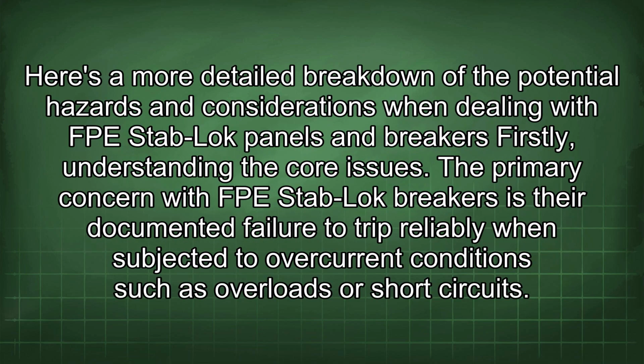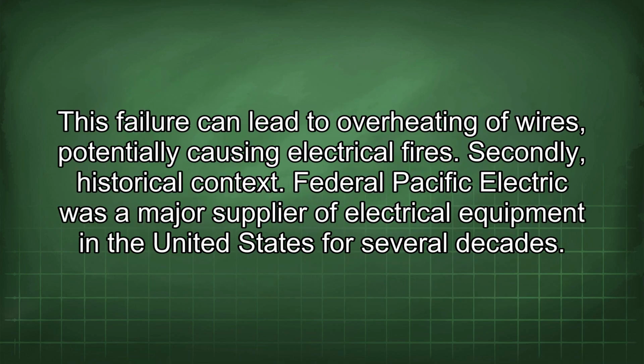Here's a more detailed breakdown of the potential hazards and considerations when dealing with FPE Stab-Lok panels and breakers. Firstly, understanding the core issues. The primary concern with FPE Stab-Lok breakers is the documented failure to trip reliably when subjected to overcurrent conditions such as overloads or short circuits. This failure can lead to overheating of wires, potentially causing electrical fires.